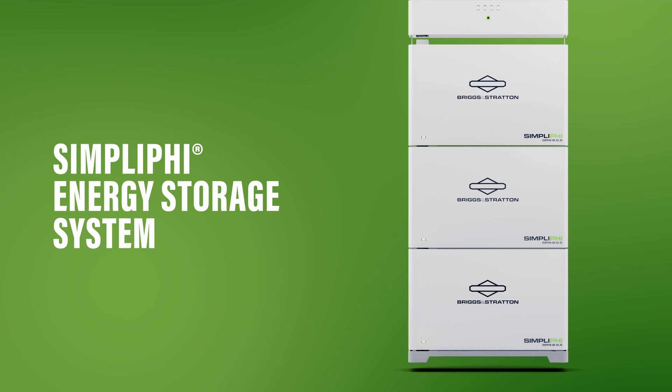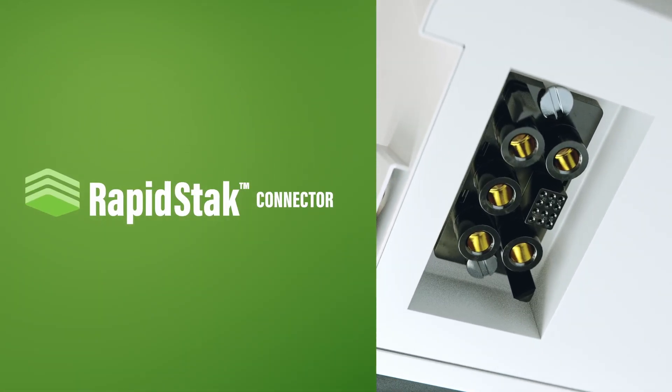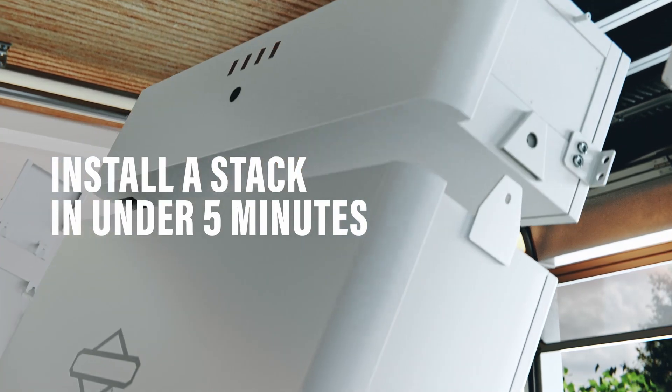It's a major shift for us as a company. Originally we were creating lithium batteries as lead-acid drop-in replacements. With the RapidStak connector, all of our power and communications come through a single connector embedded into each battery and also into the base. An installer can choose to start with either a floating wall mount or a floor base. Both options are simple to install and align. We have a self-aligning wall mount bracket included with every battery. You start with a vertical bracket that snaps into the base, then a horizontal bracket creates alignment between the batteries as they stack up, providing additional security once mounted to the wall.